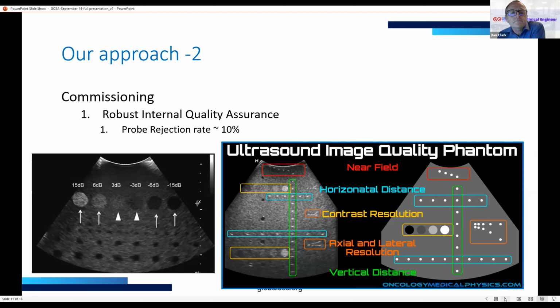It's an interesting thing to note that generally, when we're commissioning equipment, and we commission something like 5,000 items of equipment every year, we generally find over all that equipment that we get something like a 3% rejection rate, what our team refer to as out-of-box failures. So this means that some aspect of those commissioning checks have not been passed. And at that stage, we'd have to go back to the supplier, back to the manufacturer, either to get a replacement or some other way to correct that failing.